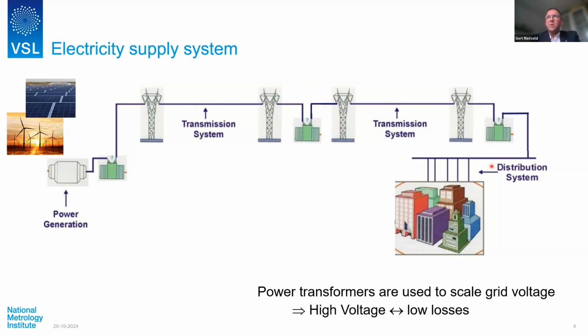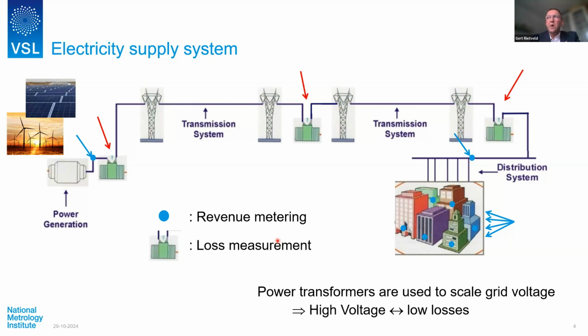When it comes to power measurement, first of all, there's metering. There's energy measurement from the electricity supplier to the transmission system operator. There's an energy measurement point when it goes to the distribution system. And of course, in our industry and our homes, we have electricity meters to measure the power. So that's the first part where power measurement comes in. Billing or revenue metering is a very important part of our electricity grids. But then the other element, and that's the focus of my presentation today, is power transformers and the losses in these power transformers.